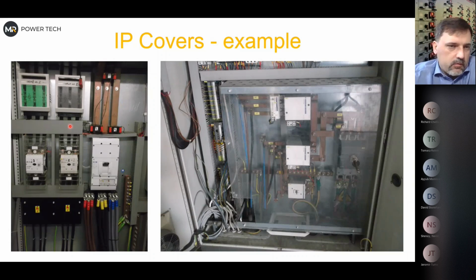On the other hand, the recommendation would be to put a plexiglass cover on it and cover it, so you cannot touch this thing. On the other hand, you see on the right side, despite it looking not that nice, this cover is very functional because it was covered from all sides. From the top and from this side, it's very hard to grab something, accidentally at least. What I would maybe add is to move the hose in front instead of back, because if something drops here, it will fall down on the bus bars. But still, this is a much better solution.